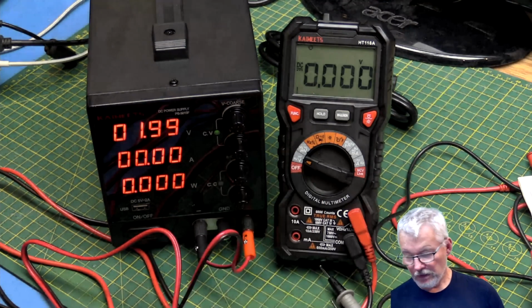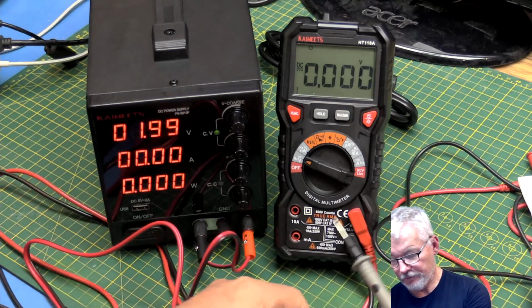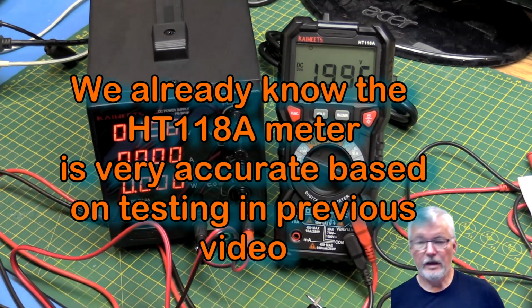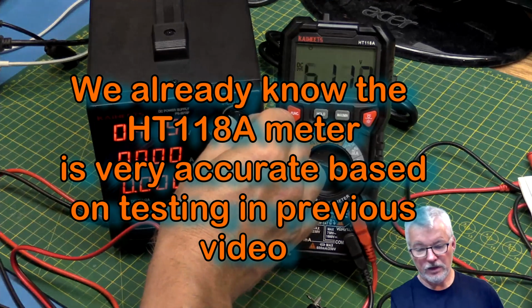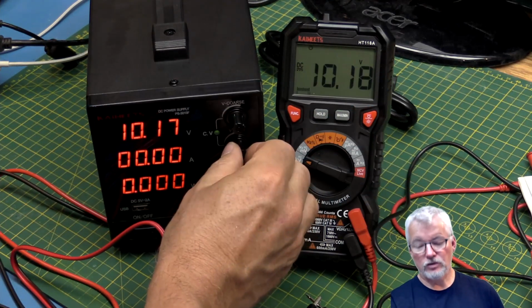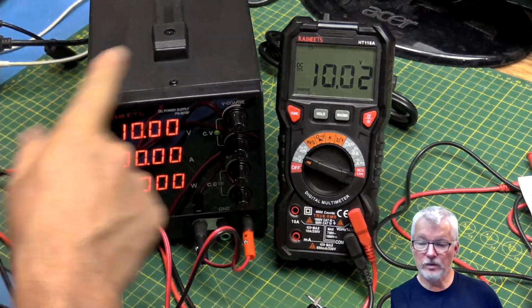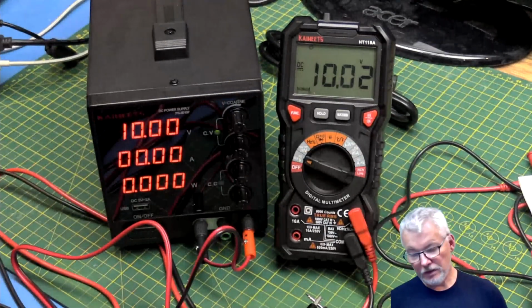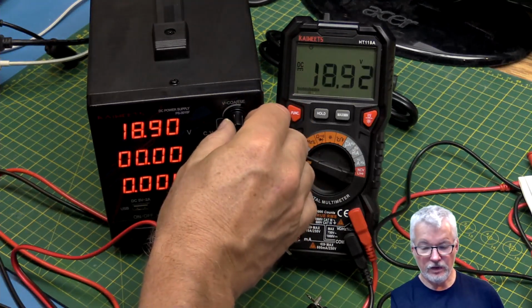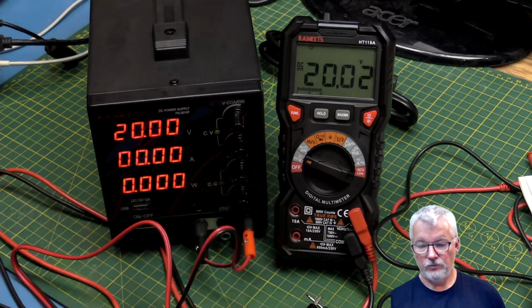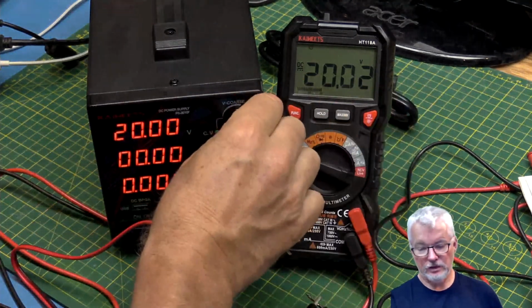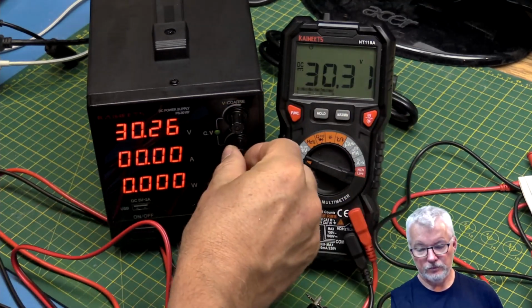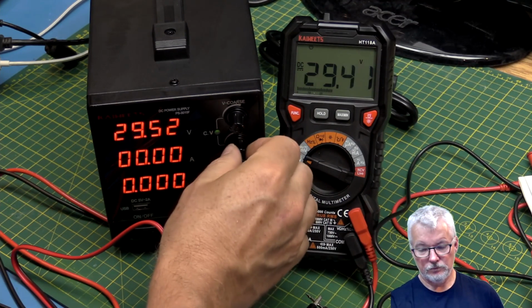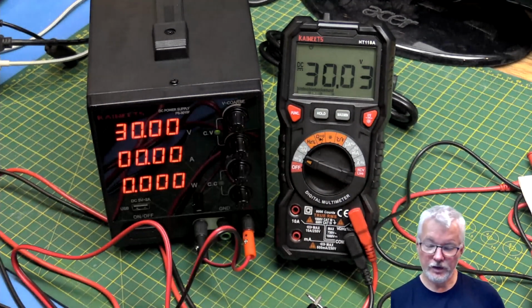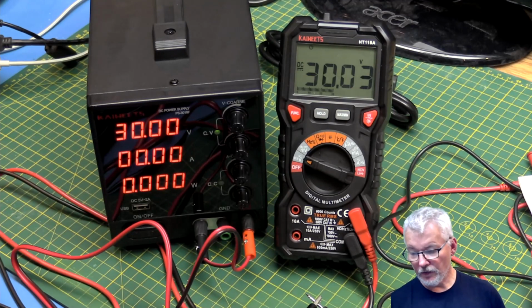So let's set it to 2 volts, and we'll hook it up to our meter. And as you can see, we've got 1.996, so that's pretty good. Let's crank it up to say 10 volts. It's actually tracking pretty good: 10.00 on the power supply, 10.02 on the multimeter, so that's pretty good. Let's go up to 30 volts. Let's do 20 volts first, why not? 20.00, 20.0, and we go up to 30. It's 30, and we got 30.03. So that's pretty good.